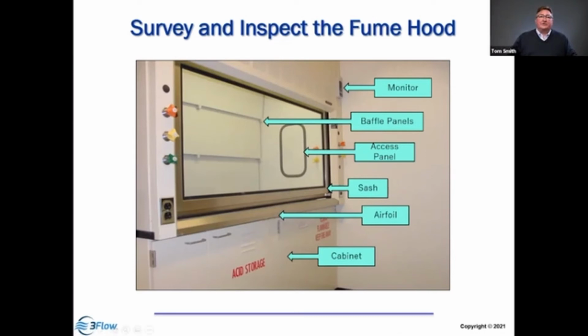And then we look at the monitor. Is the monitor properly installed? Is it energized, and is it reporting a velocity or flow or pressure? And is it functioning properly? Now, if all these features are right, then the hood should be ready to test.